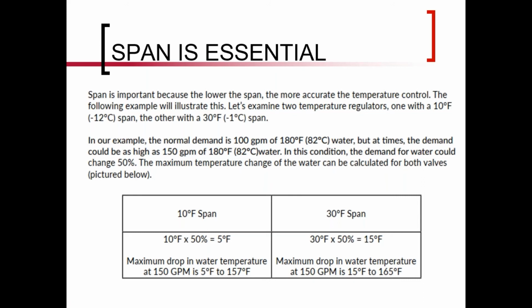So span is essential, as I mentioned earlier, and I want to point out there's a typo at the bottom of this. If you can see my cursor, that's supposed to be 175 degrees. So span is often related to the amount of stroke that the valve has. As you can imagine, a liquid needs to vaporize to stroke the valve, or if it's a cooling application, vaporized liquid needs to condense, and that takes some time. But if the valve travel is pretty short, then it doesn't take a whole lot of vaporizing or condensing to actually have an impact on that. And that's where the span becomes a big deal.